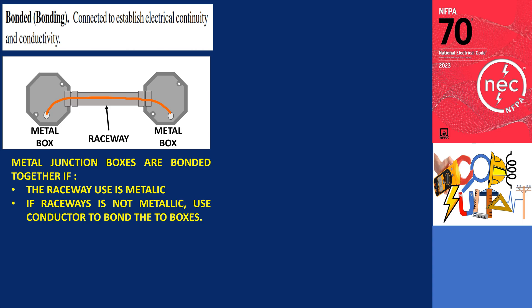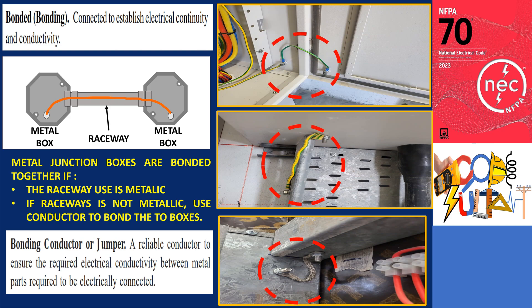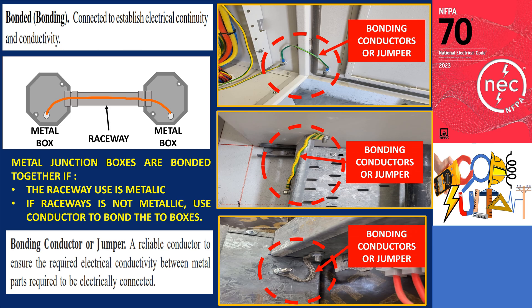What is a bonding conductor or jumper? A bonding conductor or jumper is a reliable conductor used to ensure the necessary electrical conductivity between metal parts that need to be electrically connected. They are utilized to establish electrical continuity and conductivity, ensuring a dependable connection between the metal components. Both terms, bonding conductor and bonding jumper, can be used interchangeably. Although the term bonding jumper is sometimes associated with a short conductor, bonding jumpers can vary in length, with some being several feet long.